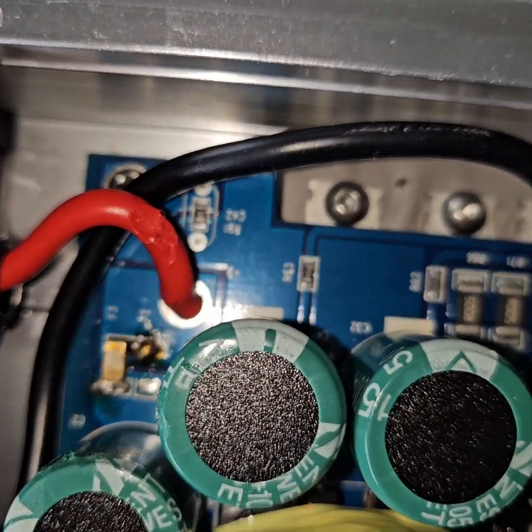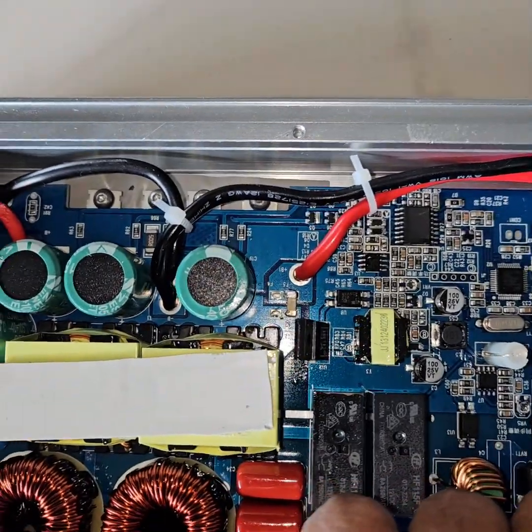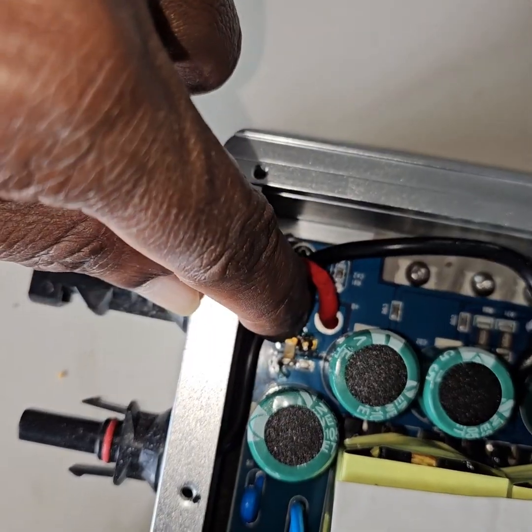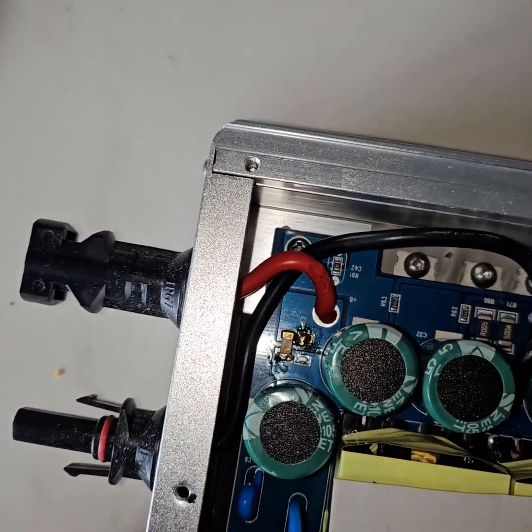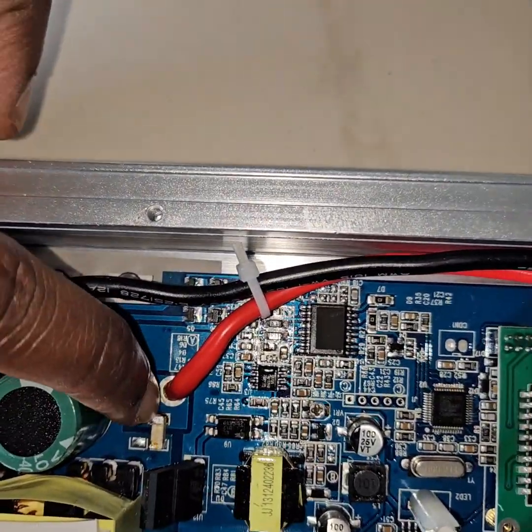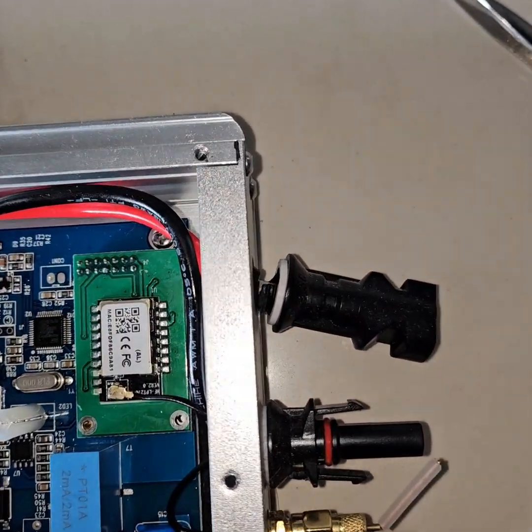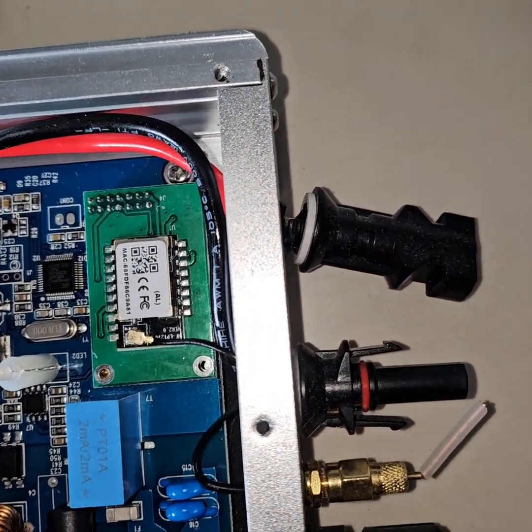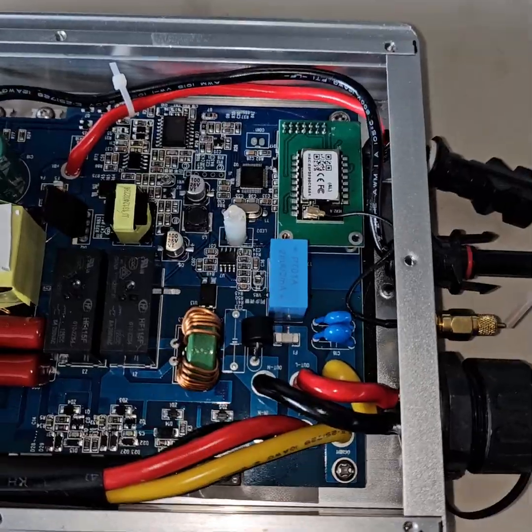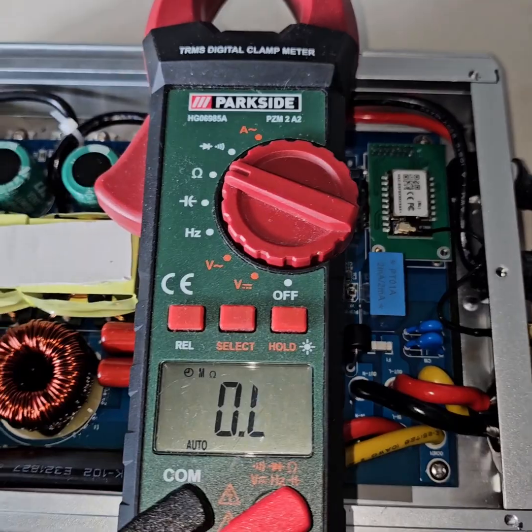So there is one DC side, a second DC side, and the AC side. You can see there is a 15 ampere fuse here. One DC side, the other DC side comes here - again there is a fuse which is 15 ampere. And there is a third fuse which is the AC side. Let's check whether they are all right or not.